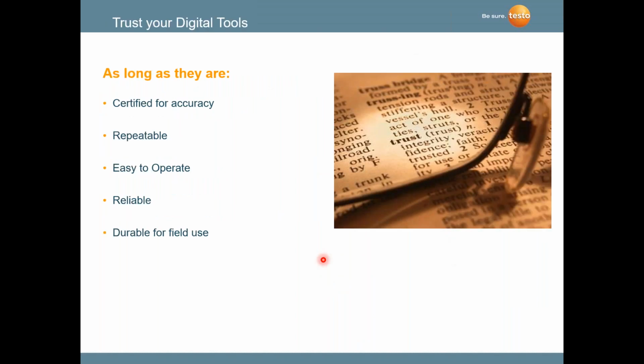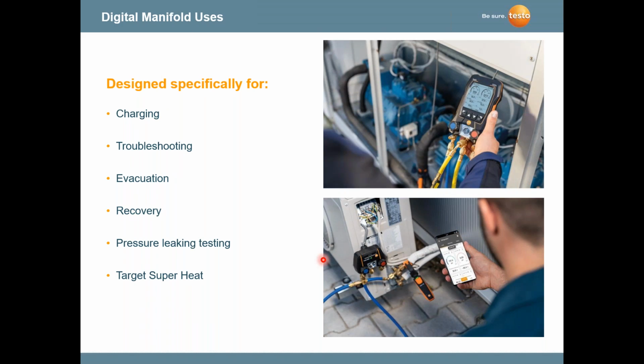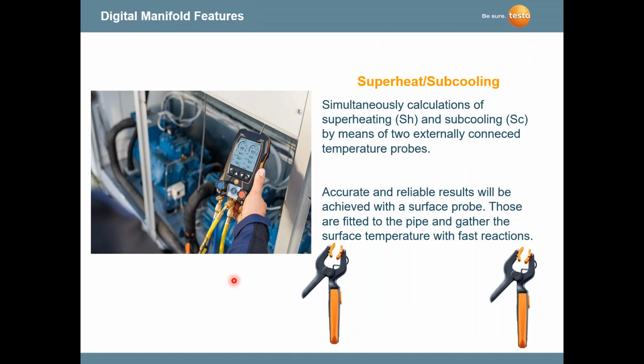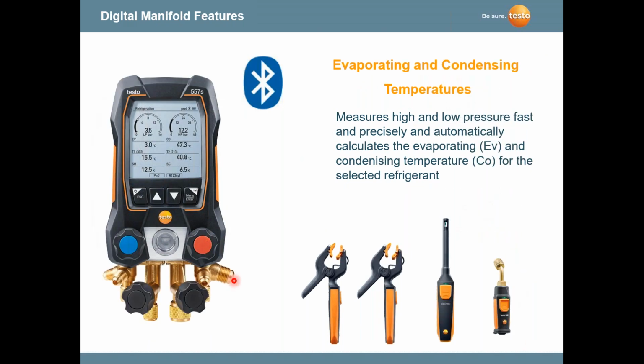So, again, digital instruments have been here for a long time. I think certainly the digital gauges were, as I indicated, introduced about 15, 16 years ago. Improvement has taken place over time. The cost of these instruments is very affordable, which I'll talk to you a little bit about as I go through some of this. But these are used in a variety of different methods, not only charging, but troubleshooting, pulling a vacuum, recovering, doing a positive pressure leak test using nitrogen, looking at what we talked about, targeted superheat. We talked enough about how these instruments calculate superheat and subcooling simultaneously. We talked a lot about evaporation and condensing temperatures.